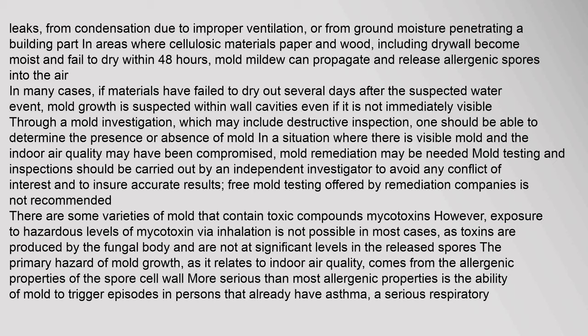In many cases, if materials have failed to dry out several days after a suspected water event, mold growth is suspected within wall cavities even if it is not immediately visible. A mold investigation, which may include destructive inspection, may be needed to determine the presence or absence of mold where indoor air quality may have been compromised. Mold testing and inspections should be carried out by an independent investigator to avoid any conflict of interest. Free mold testing offered by remediation companies is not recommended.